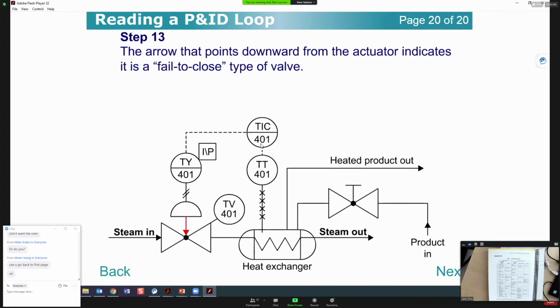If something in this control loop, let's say the electrical signal line or air line, becomes damaged, or you have a problem with that line, for this process, if this valve keeps supplying the steam, it will cause damage to the process. Or for certain processes, if you don't have the steam coming in, maybe the material here gets too cool down. It also can cause damage to the whole process. So that's where you pick those valves, either fail to close or fail to open. It depends on the process requirement. Later on we're going to talk more about fail to close or fail to open.